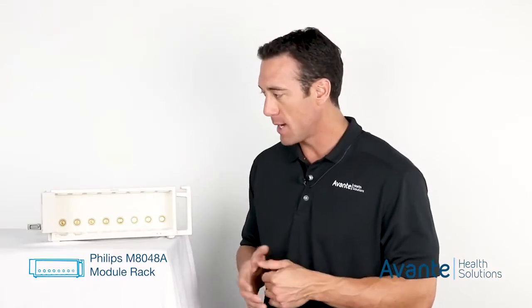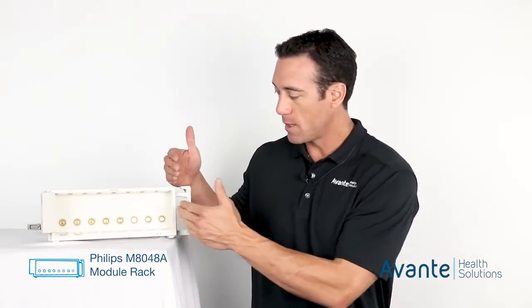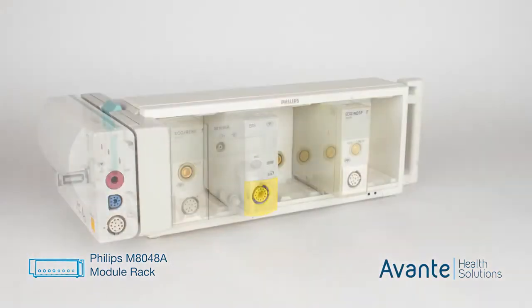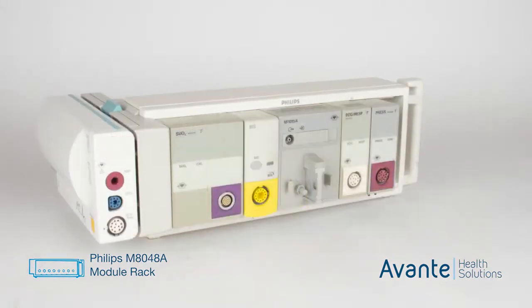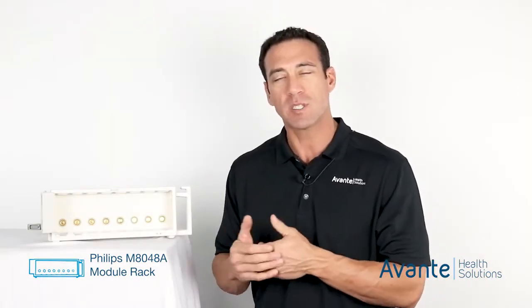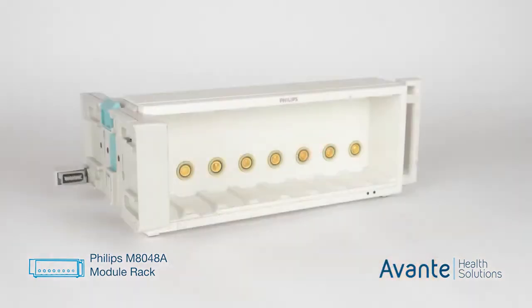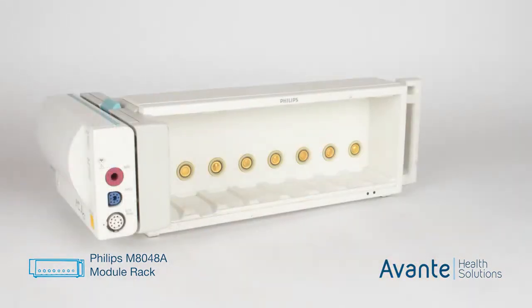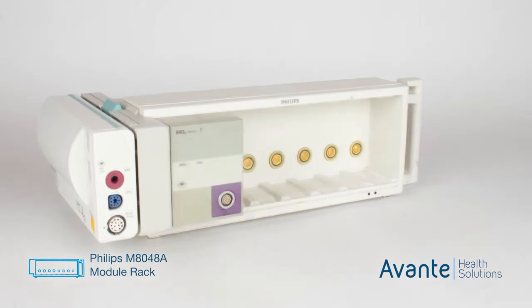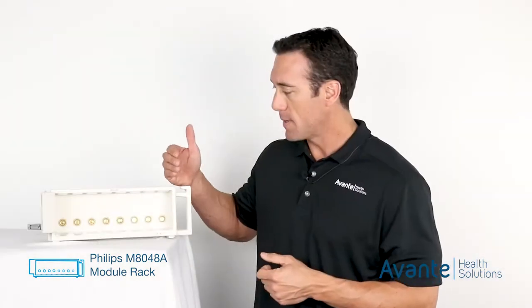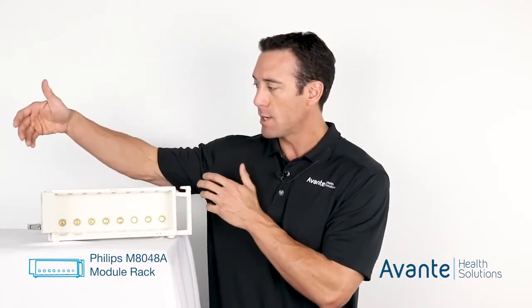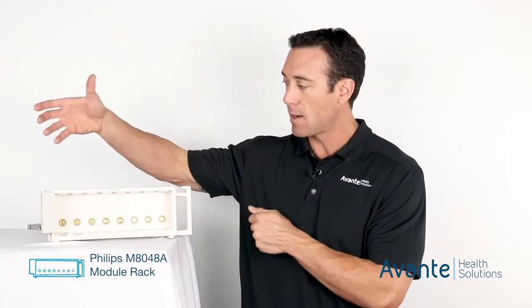Basically, we can put in all of our individual parameter or measurement modules as the physician calls for. They may need a spread of certain types of modules, things like NIBP, SpO2, ECG. They may also want more unique measurements like SVO2 or even BIS monitoring. This connects to the monitor and allows those measurement modules to be displayed on it.